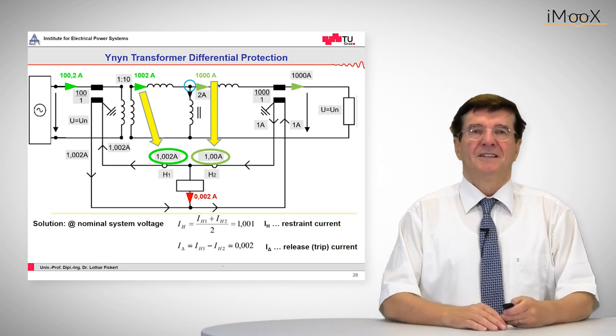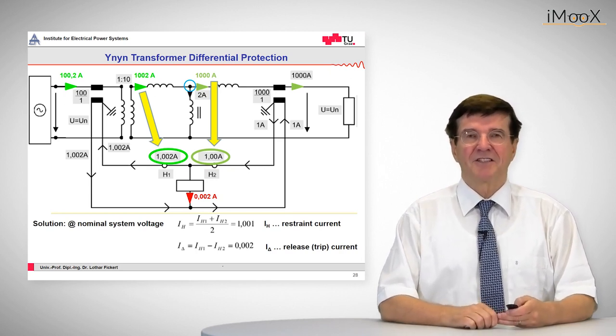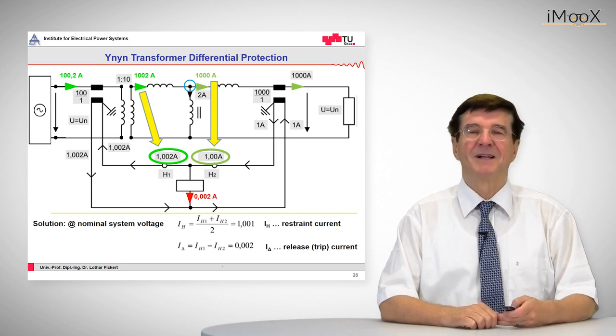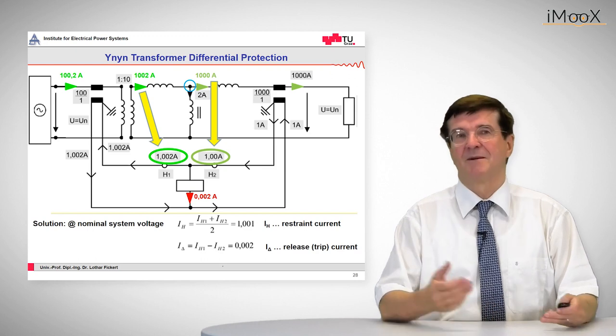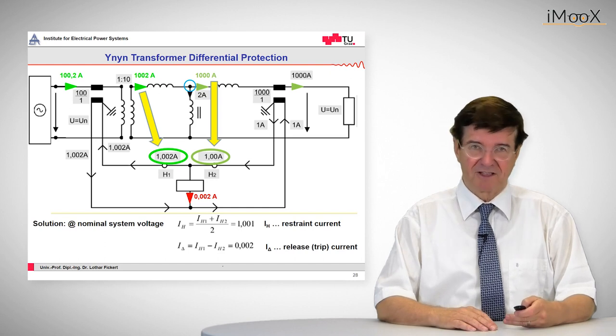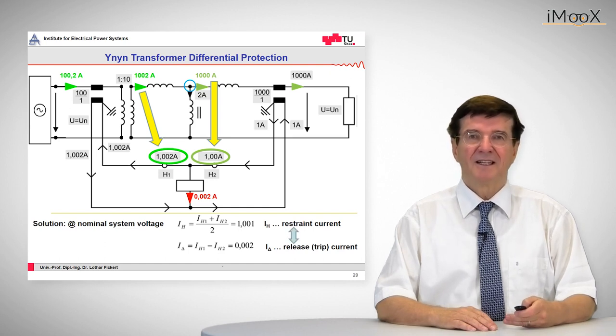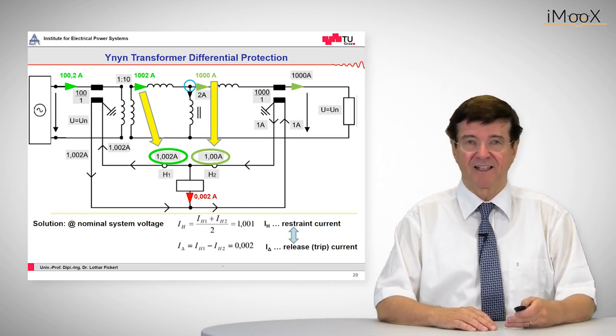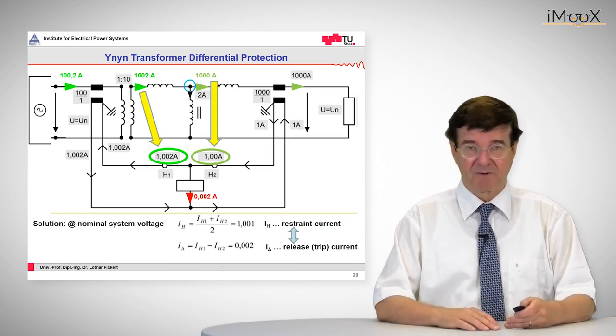So here the remedy and remedial measure is to introduce the so-called stabilizing current, the restraint current, which is made up of the sum of both the incoming and the outgoing current, and this is compared to the release differential current. If the ratio is very small, then it is thought to be an inaccuracy and nothing happens. If it is large, then a trip occurs.